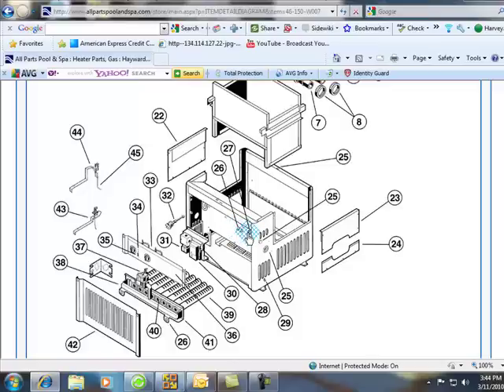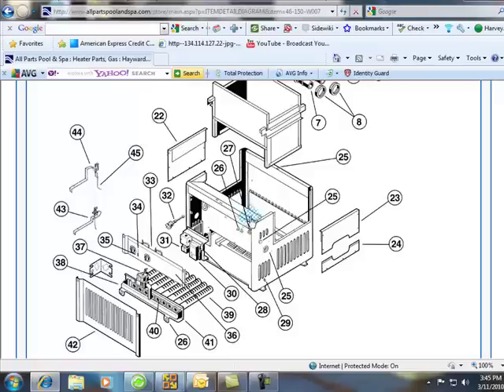This is the pressure switch. Keep in mind if you're checking the pressure switch for continuity, you have the water running through it.